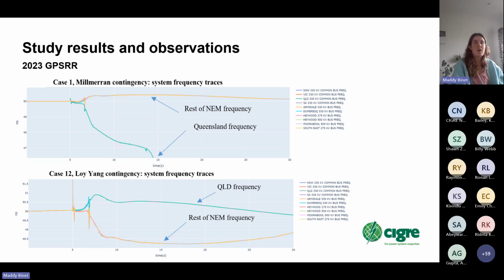This also highlights the importance of UFLS and the need to ensure adequate UFLS to prevent system collapse following major contingency events. Following on from this, we completed some sensitivity studies looking at tripping load in Queensland or New South Wales following fault clearance to try and prevent Queensland from losing synchronism with the rest of the NEM and QNI from exceeding its stability limits.